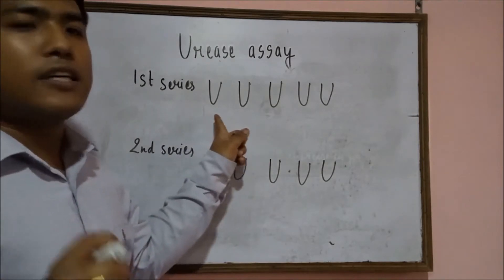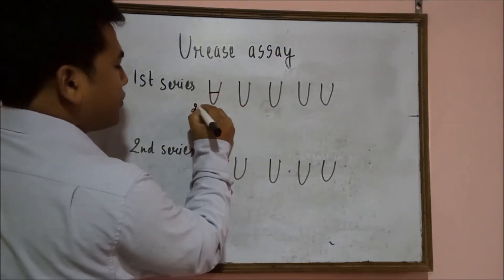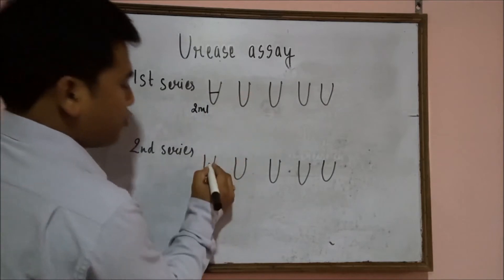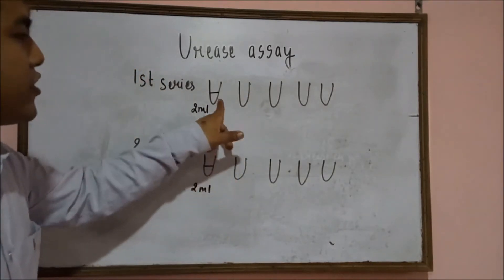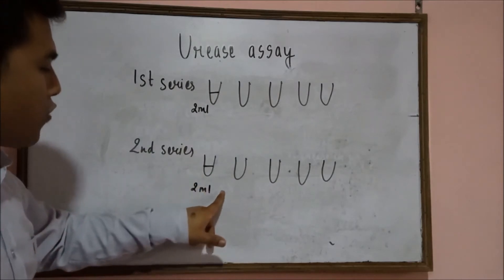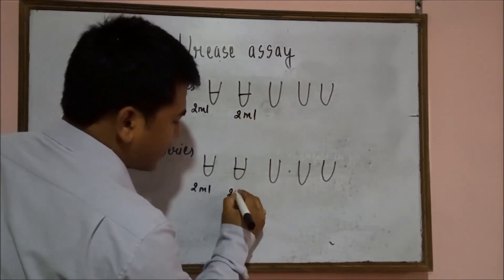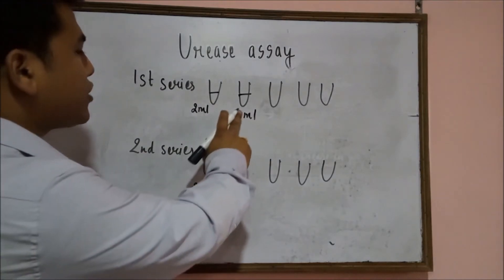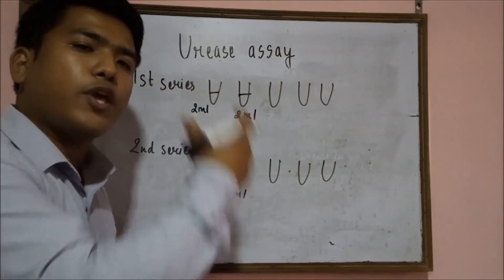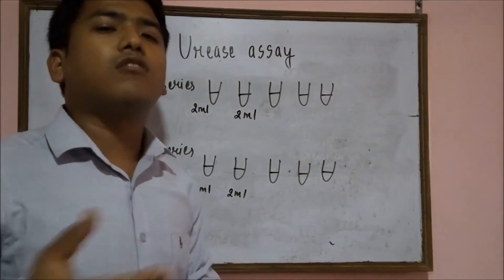The concentrations must be in increasing order. You add 2 ml of the calibrator into each tube. The concentration must be the same in the first test tube of the first series and the first test tube of the second series. Similarly, you add 2 ml of the calibrator in the second series, and the concentrations of corresponding test tubes across both series should be equal. Note that the volume of 2 ml is just an example; you can take the volume of calibrator according to your need.